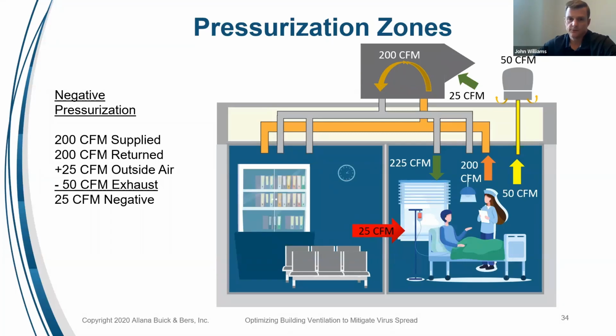We exhaust 50 CFM from the room. By putting an exhaust fan of 50 CFM in the room, we now supply 225, we return 200, but we're going to exhaust 50. Now, any disease or hazardous materials, anything that may be in that room that we don't want to spread to the room on the left, we're going to contain in that room as we're going to pull a negative into that room. It's very important that we understand where our pressurization zones are.